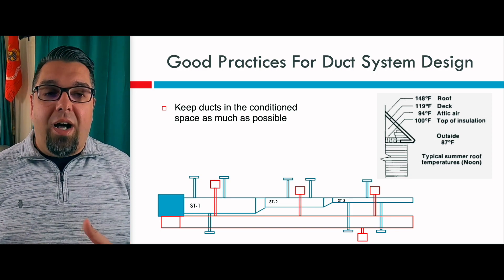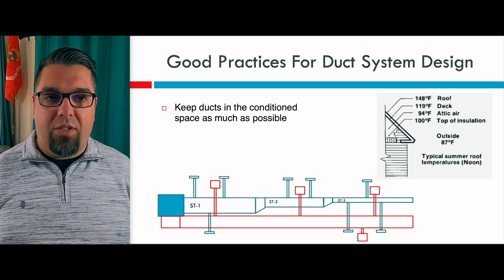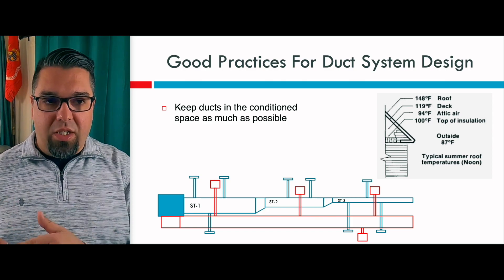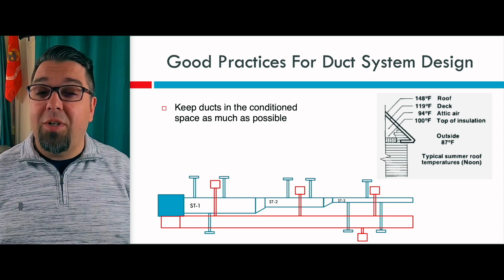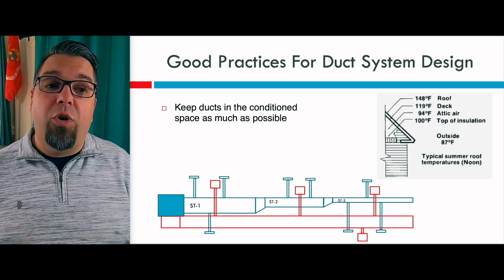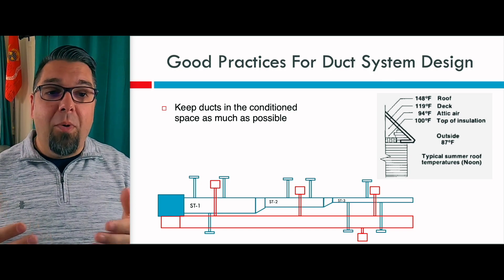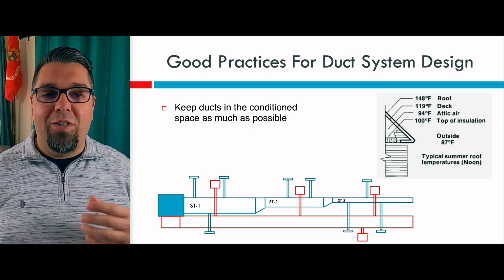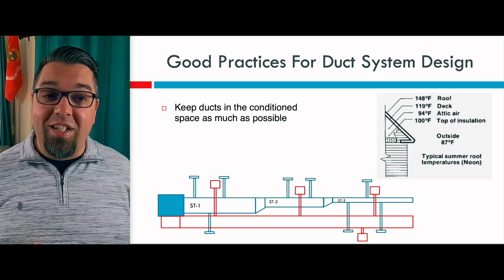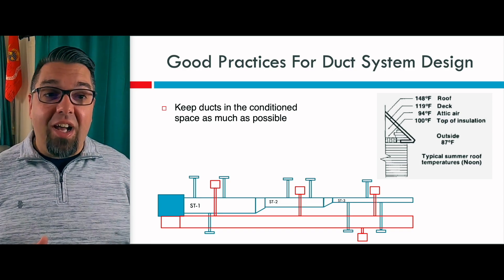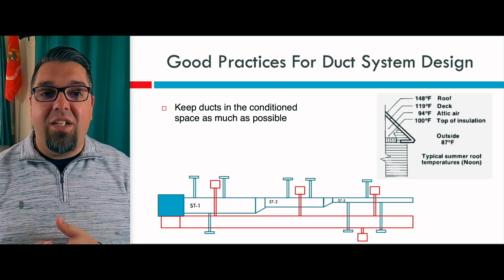You can see in the image here on the right, the temperature of the attic air is typically anywhere from 7 to 20 degrees more than the temperature outside. As an example, if you don't rest your duct work on top of the insulation but actually suspend it in the attic — which we don't really want you to do — the attic air could be about 94 degrees. If it's 87 degrees outside, that's your design temperature. If you're from the northeast, 87 degrees outdoor design temperature is typically what you're designing to. If it's warmer than design days, it's warmer in the attic. The roof deck could be as much as 32 degrees warmer than outside — so if it's 87°F outside, the roof deck could be 119 degrees.